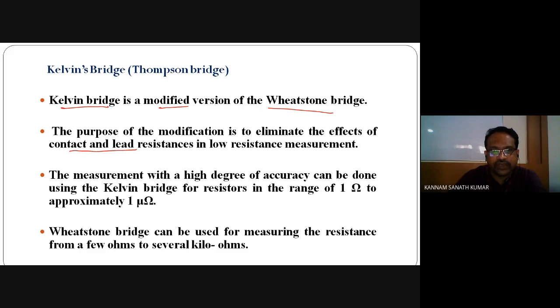By using the Kelvin bridge, we can find the lead resistance or contact resistance. We can do low resistance measurement, and it has a high degree of accuracy. The Kelvin bridge can measure the resistance from 1 ohm to approximately 1 micro ohm.